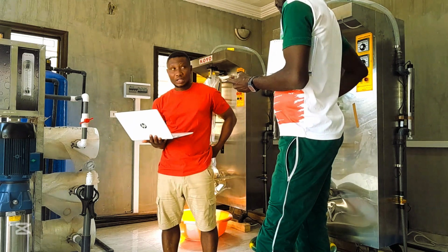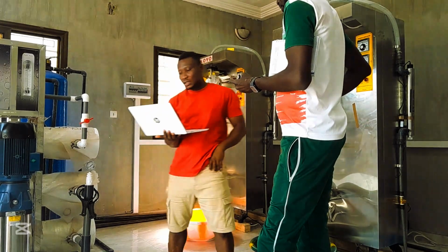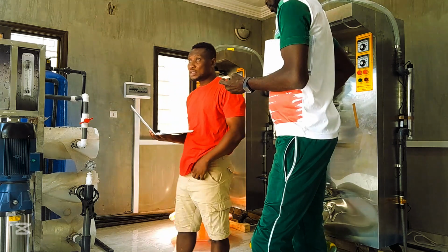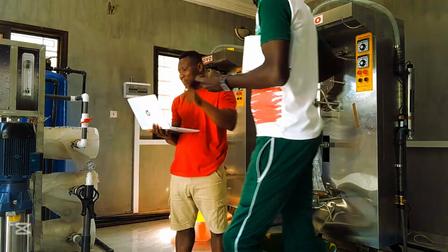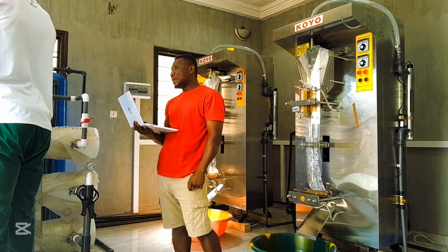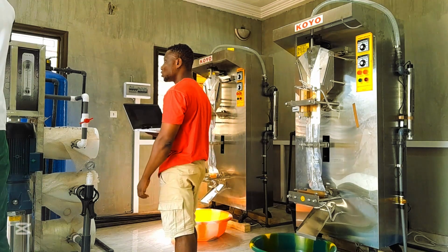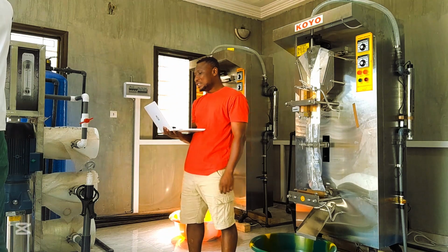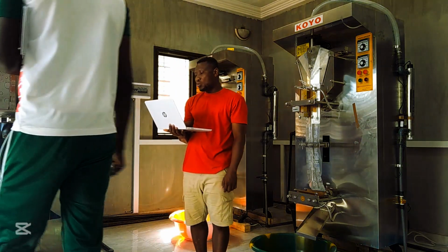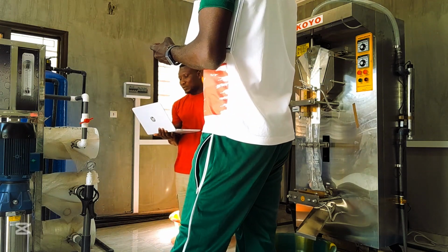Now we said that you monitor the tanks. After treatment is done, first turn off the pressure pump, followed by the feed pump. Then turn the main switch off, on the inside. Lastly, close the air valve to make sure water doesn't flow. If that happens, you will waste the water through the waste line.